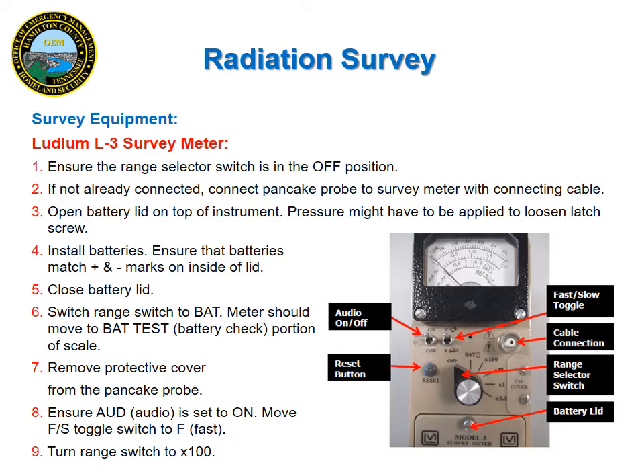If they are good, remove the protective cover on the pancake probe. And then you will want to make sure that the AUD, which is the audio, switch is set on, and the FS switch is set to fast, which is the F. To begin the operability test, return the range selector switch to times 100.